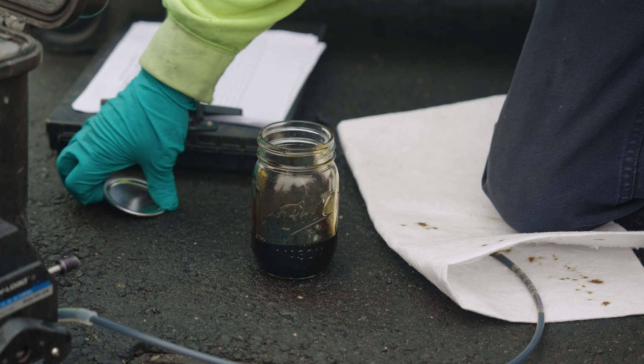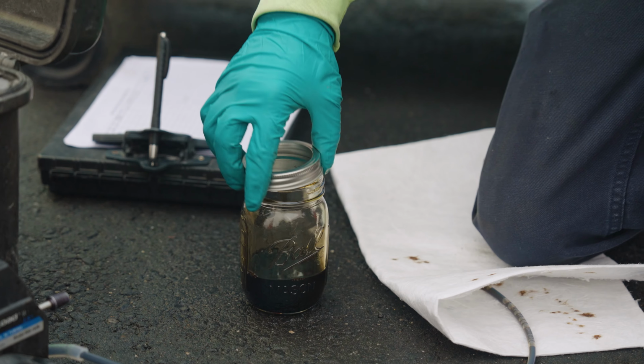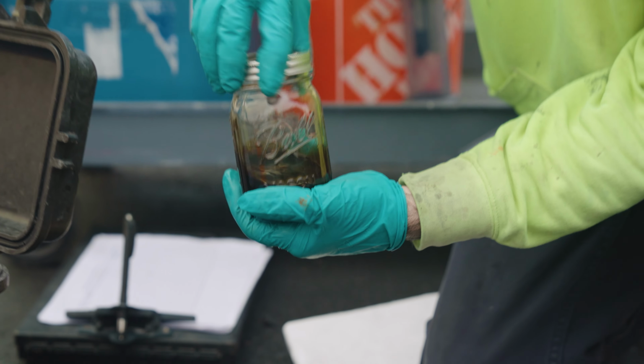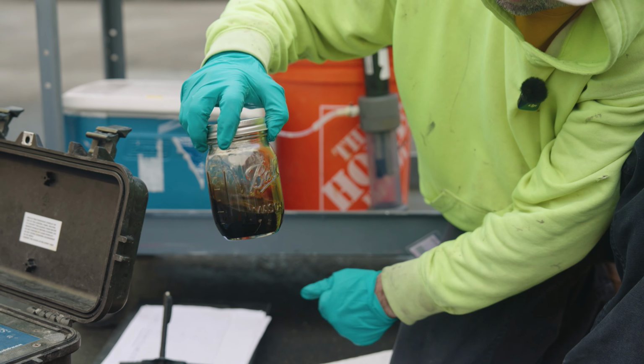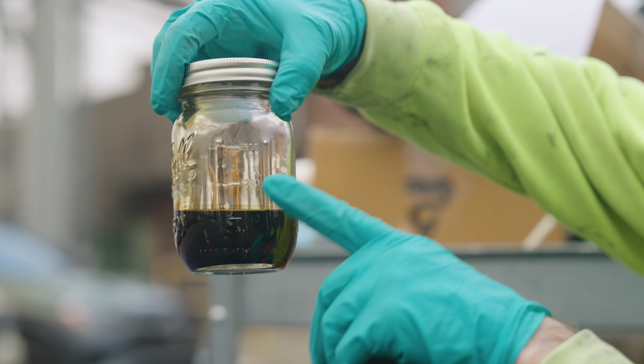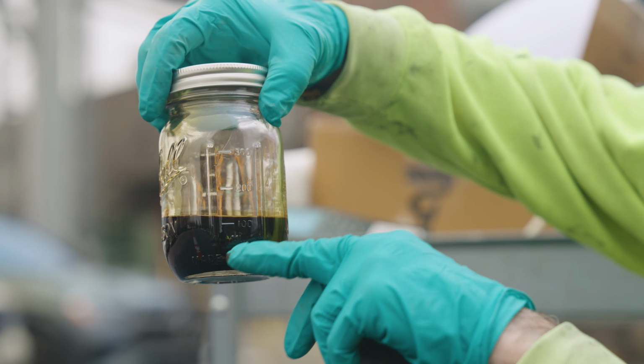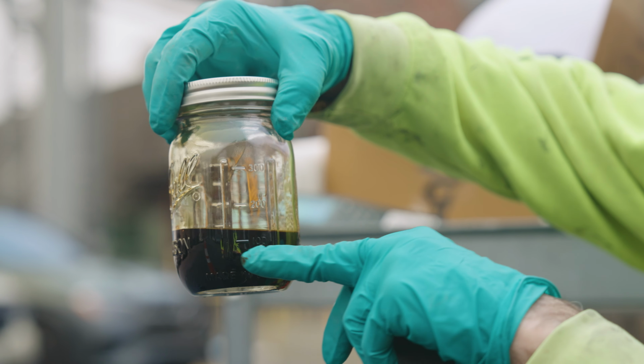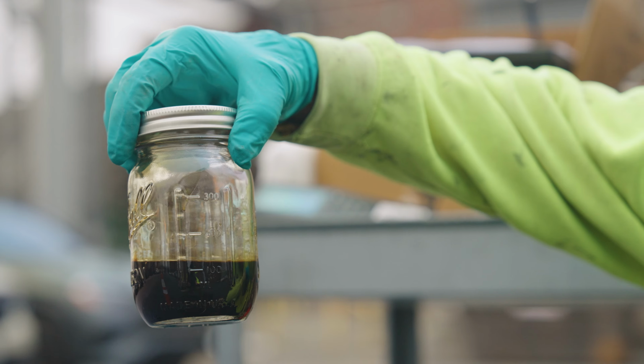Let that sit for a minute or so and see if any water settles out, and then we'll put that into our vials, our unpreserved vials, for fingerprint analysis. You can see this is all pure oil. There's no separation of water. If there's water in this sample, it'd be on the bottom with the oil floating on the top. So that's what we're looking for, is pure oil.